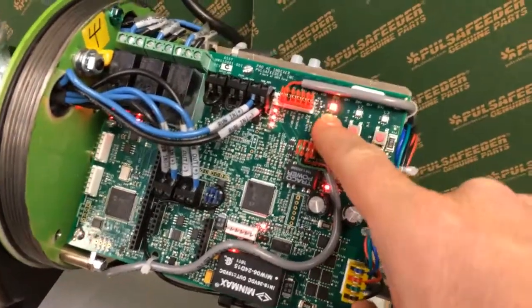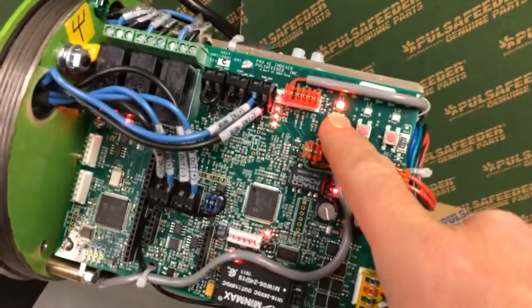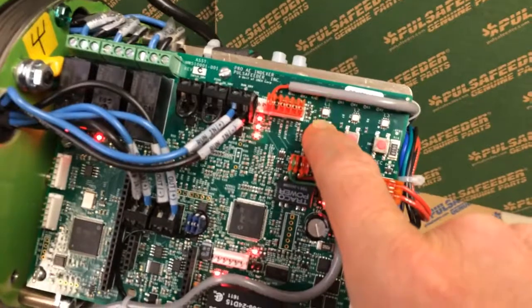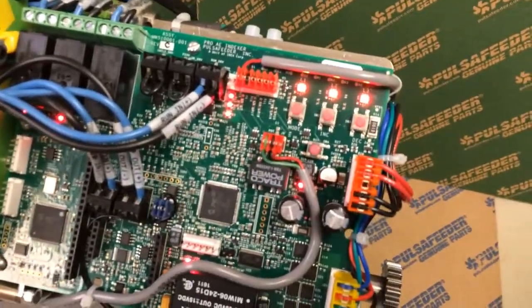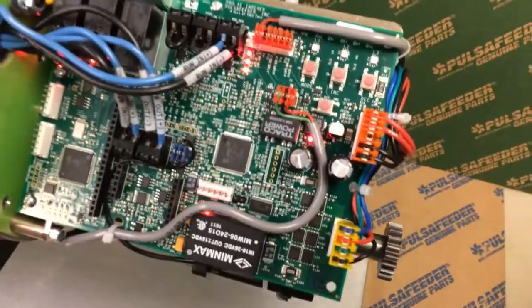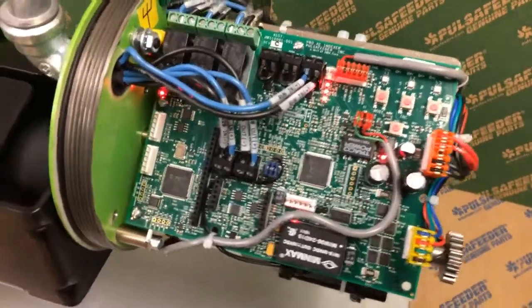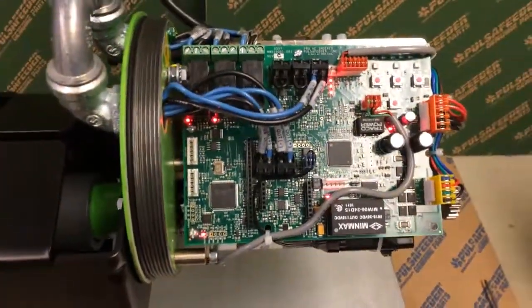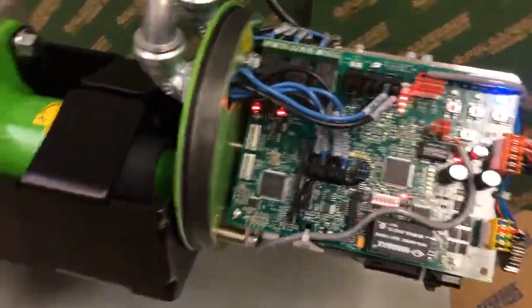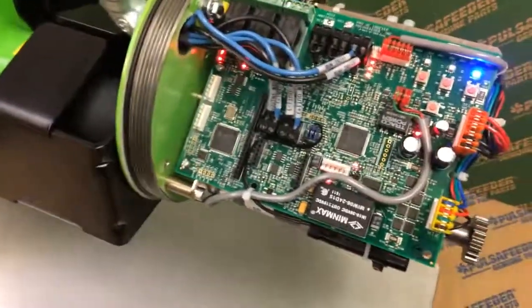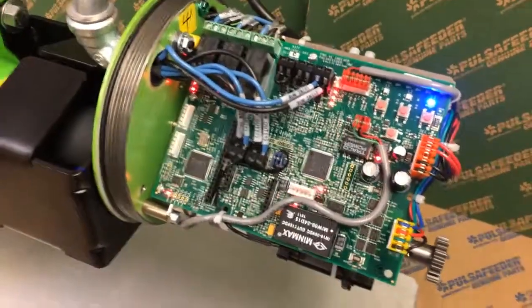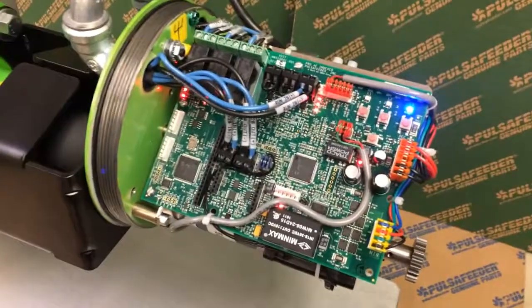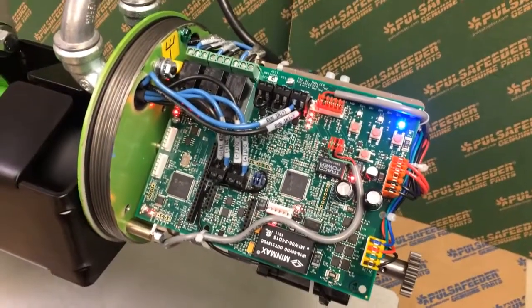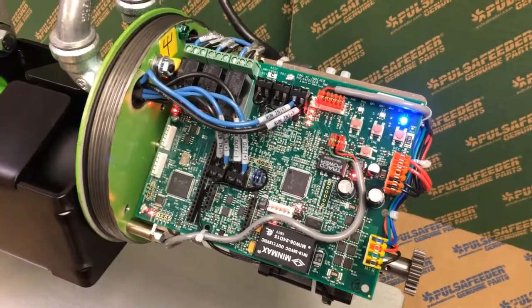Now this unit is just waiting for me to say, okay, I'm done. I'll press it one more time. We get 3 red LEDs, which indicates that we're saving the value away, and we're done. That's the end of mechanical calibration. You'll notice the 3 blue LEDs came on. After mechanical calibration, we reset the processor board, so we start over. All our values are saved away, and now we're ready to roll.